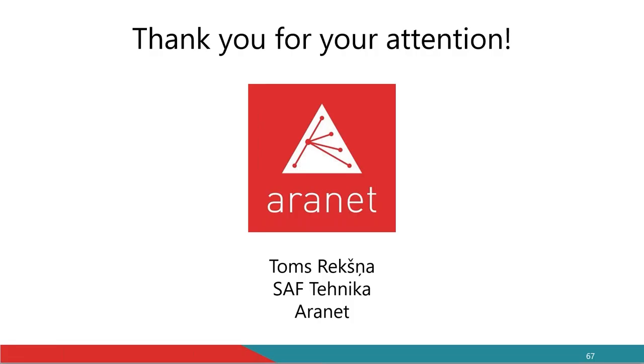I see two questions. Would you recommend using more than one CO2 sensor in one room if the number of people surpasses a certain number? Typically what we see with CO2 sensors is that if we're not talking about very huge rooms, then one per room should suffice. Because especially if there's people there that are breathing, that are moving around, that really creates diffusion, which means that this CO2 is being circulated around. And in general, it's quite hard to make a ventilation for a room where half of the room is ventilated and the other half is not ventilated.